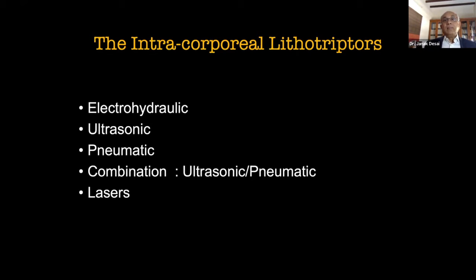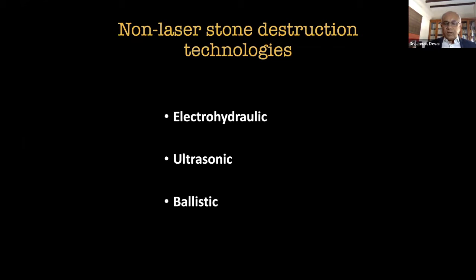And then, of course, miniaturized PCNLs came in, flexible ureteroscopy came in, where you had to put in instruments, or rather the breaking devices, which would go through those flexible routes, and that was laser. The laser fiber is the only energy which goes through a flexible instrument. The powerful energies are ultrasound or pneumatic. The mechanical will not go through the flexible route. So let's discuss all this one by one. Essentially, the non-laser forms of technology were electrohydraulic, ultrasonic, and ballistic. Electrohydraulic has been given up; ultrasonic and ballistic are very much here to stay.